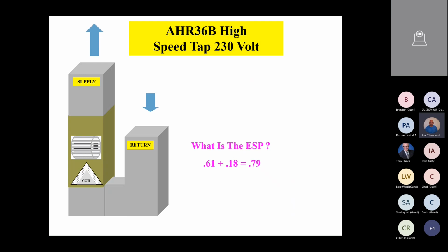And so this is another reason I like to take the readings separately, because right now on this one here, the obvious one is the 0.61. That was supply. So somewhere on that supply, maybe we have a kink in the supply duct. Maybe it's some duct board that's folded in. You could have a situation where grandma has some rugs or something thrown over the supply registers, whatever. So you're going to need to investigate, because you've got pretty high static pressure, very high static pressure on the supply, in this case of 0.61.